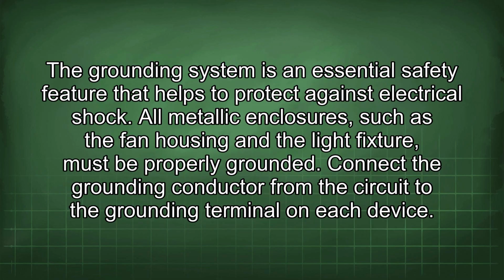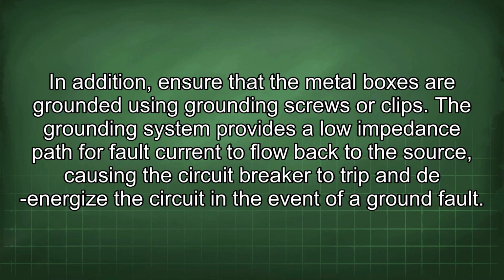The grounding system is an essential safety feature that helps to protect against electrical shock. All metallic enclosures, such as the fan housing and the light fixture, must be properly grounded. Connect the grounding conductor from the circuit to the grounding terminal on each device. In addition, ensure that the metal boxes are grounded using grounding screws or clips. The grounding system provides a low impedance path for fault current to flow back to the source, causing the circuit breaker to trip and de-energize the circuit in the event of a ground fault.